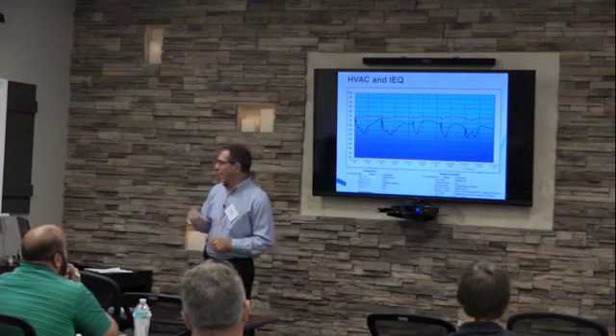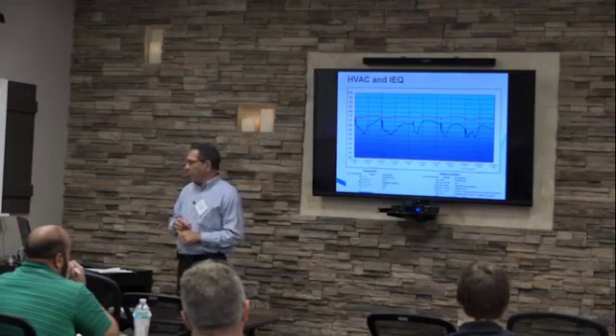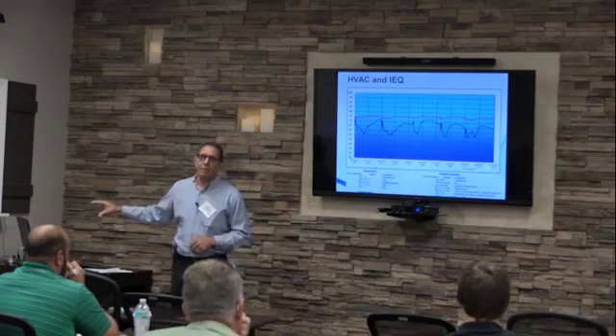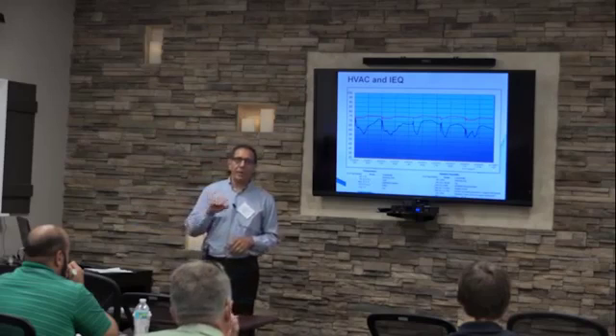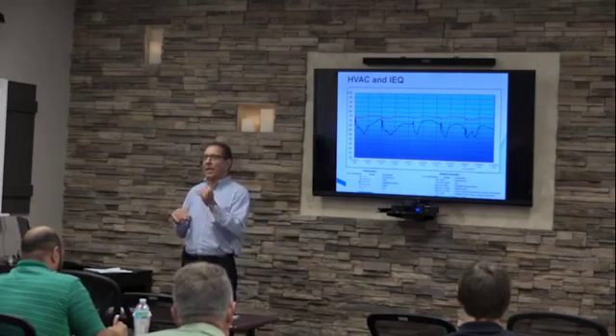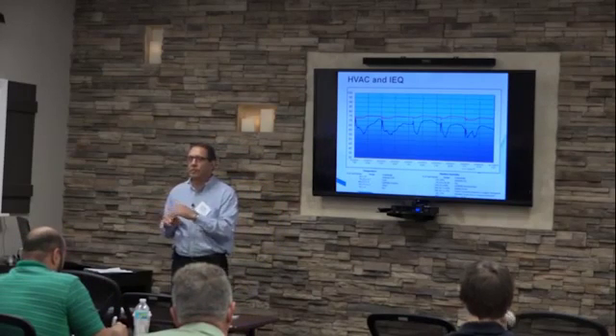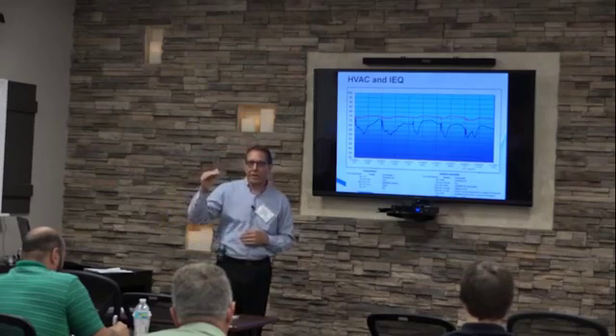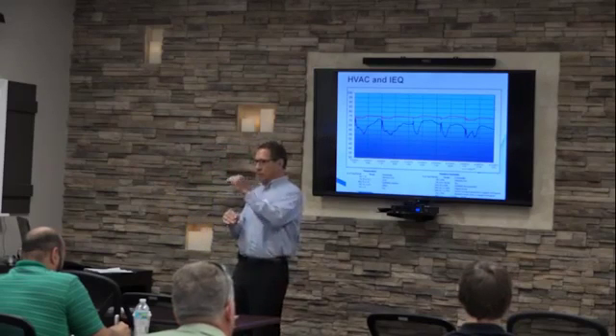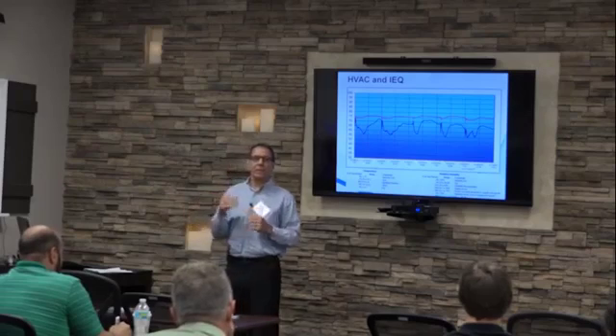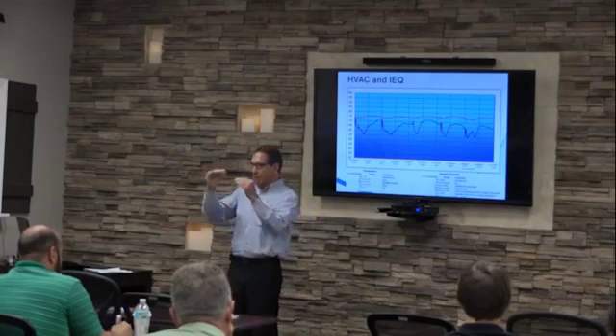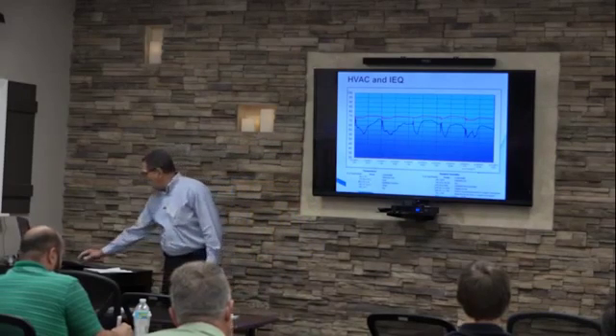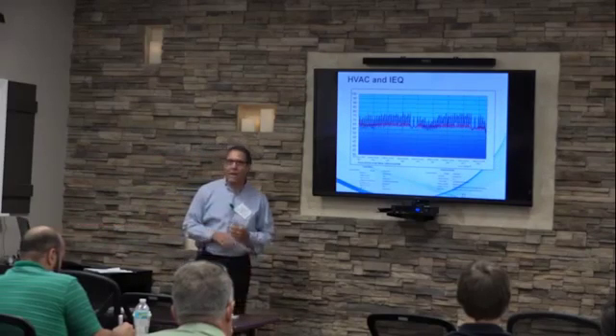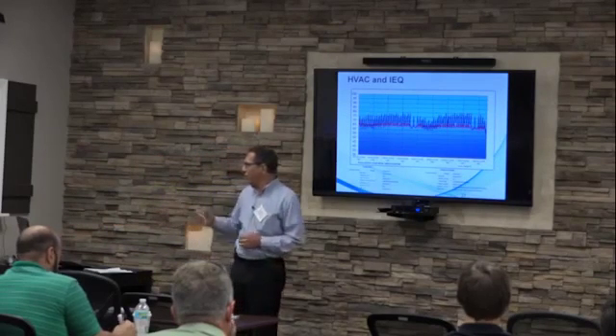Through building diagnostics, we can find a number of possible situations from this chart. With this specific graph, we found that when they cycle off the air conditioning system, the exhaust system keeps running overnight, which raises the relative humidity. It brings the building pressure negative and increases the relative humidity.